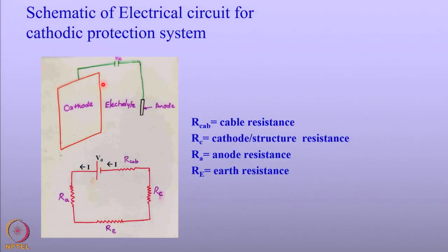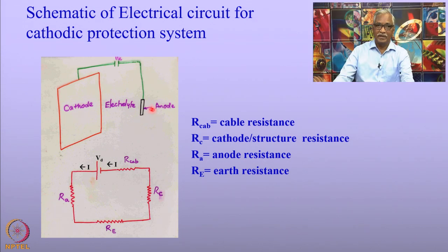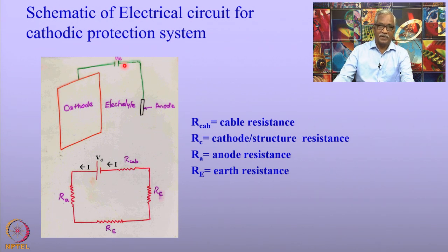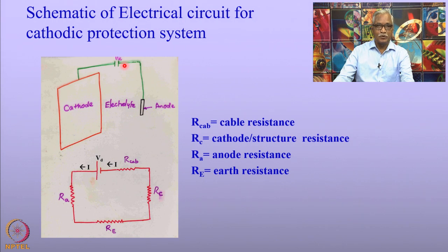Before we discuss stray current corrosion, let us go back to cathodic protection in general. What is shown in this diagram is a schematic of cathodic protection of a structure involving an anode and a cathode, and of course a DC source — a rectifier. I have used a rectifier here because stray current corrosion mostly occurs when structures are protected using an impressed current cathodic protection system.